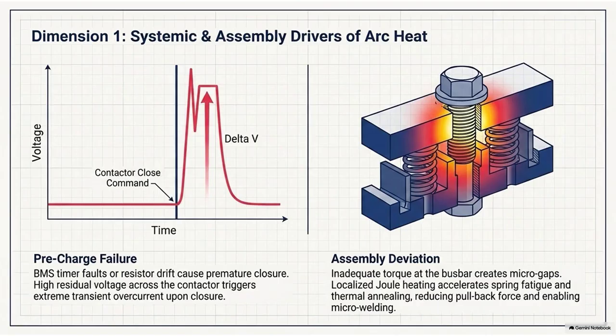Now, copper is an exceptional conductor of electricity, but it is equally exceptional as a conductor of heat. Oh, I see where this is going. So the copper bus bar isn't just carrying the electricity. It's acting as a thermal highway, actively pumping that friction heat directly away from the loose bolt. And unfortunately, it often conducts that localized heat straight down the bus bar and directly into the internal, highly sensitive structure of the high-voltage relay itself. The switch we were just talking about.